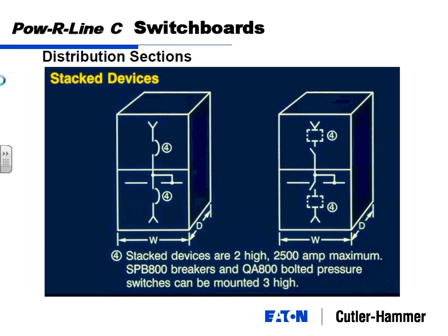All switchboards are building blocks on a distribution section other than the main. You may have larger than 1200 amp breakers. So the chassis can hold a 1200 amp molded case breaker, but if you get to a bigger breaker, like if I've got a 4000 amp main and two 2000 amp feeders, there are different ways you can do that, different options of mounting one on top of the other or what have you to get that configuration done.